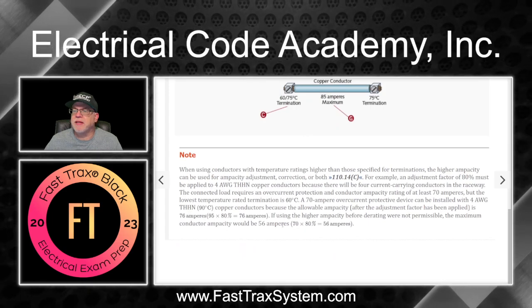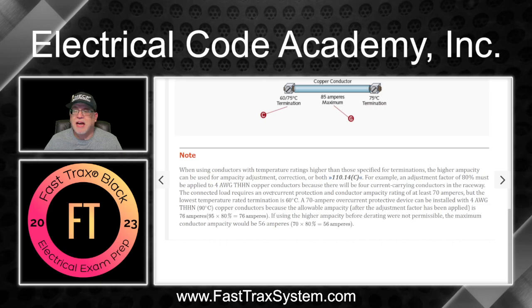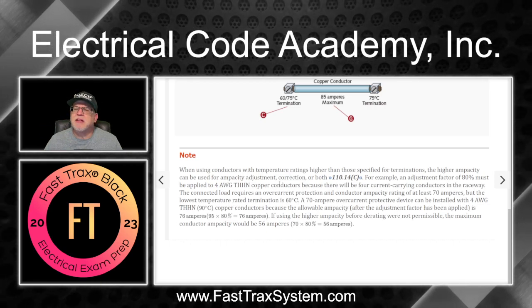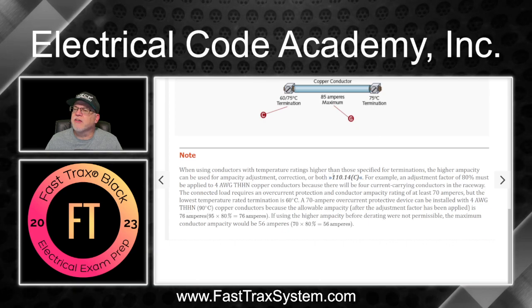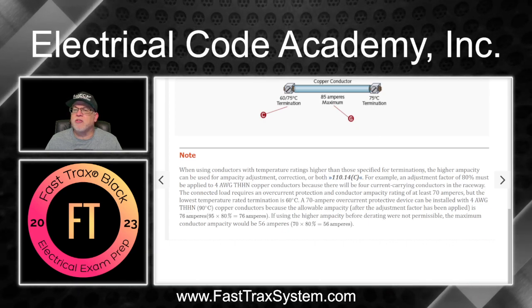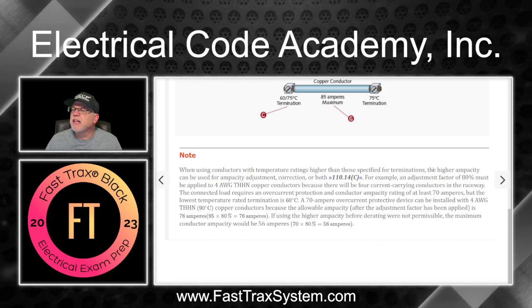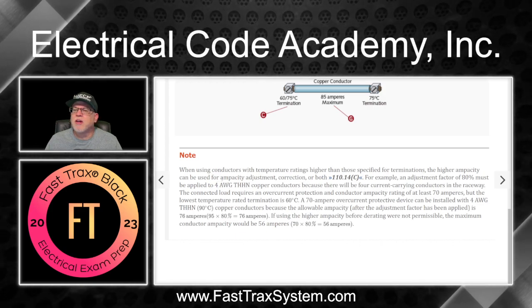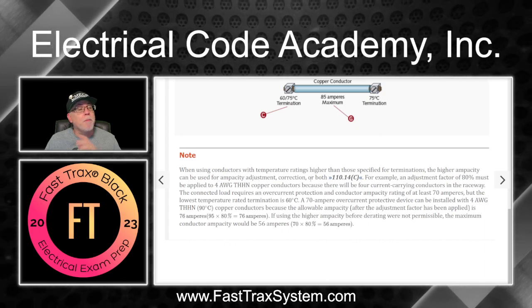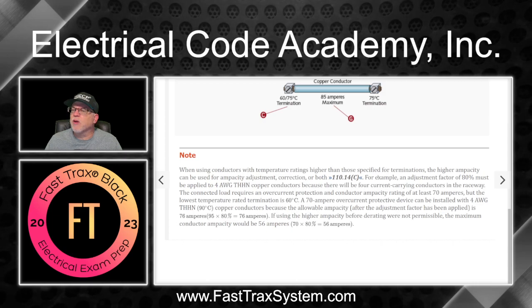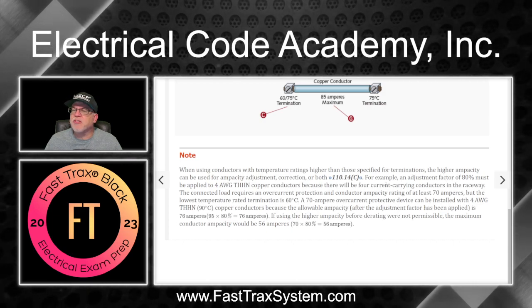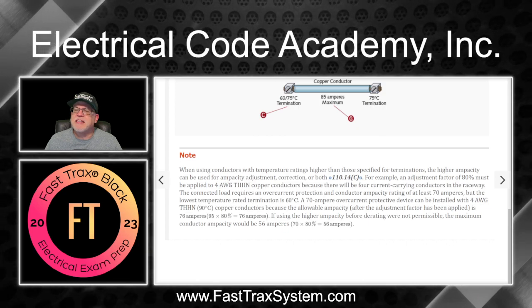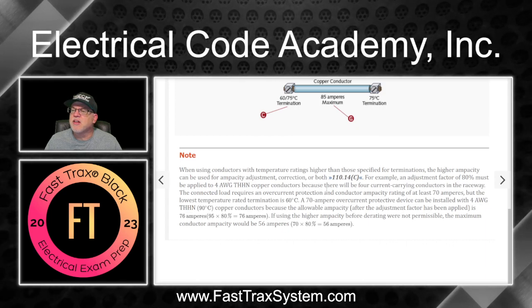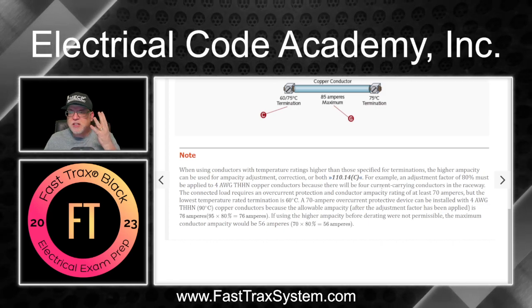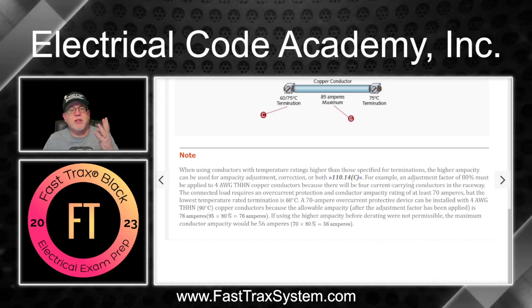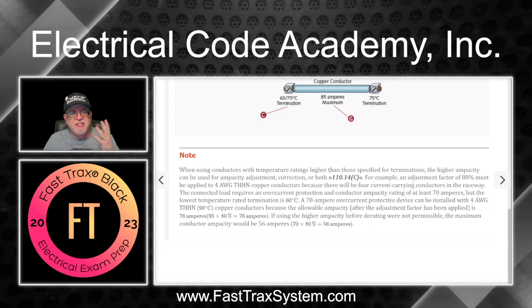All right, a little extra tidbit here. We'll just throw this one out at you. I'll read it to you. I know the script is very small, but it says, when using conductors with temperature ratings higher than those specified for terminations, that means using the 90-degree rated insulation, for example, the higher ampacity can be used for ampacity adjustment, corrections, or both. So 110.14(C), for example, an adjustment factor of 80% must be applied to 4 AWG THHN copper conductors because there will be 4 current-carrying conductors. Now, this is in accordance with 310.15(C)(1), by the way, so we're just giving you an example.